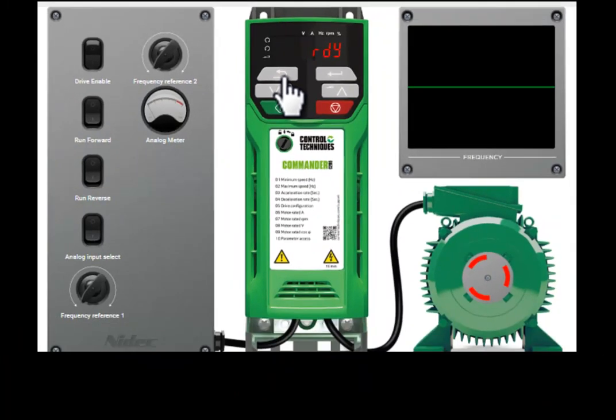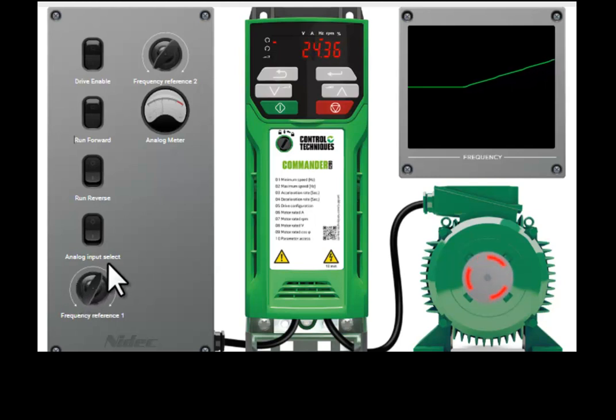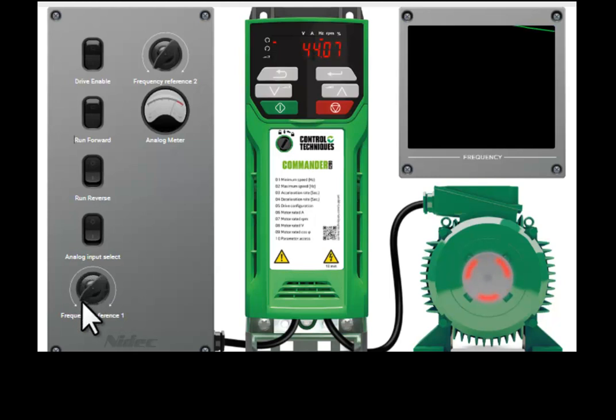Now we will operate the motor using the Nidec drive in external operation mode. The external terminal has run forward and reverse inputs, and an analog reference input connected to a potentiometer. When we increase the reference, the motor speed increases up to 58 Hz — the maximum speed frequency we set. When we decrease it, the frequency decreases down to 5 Hz — the minimum frequency we set.